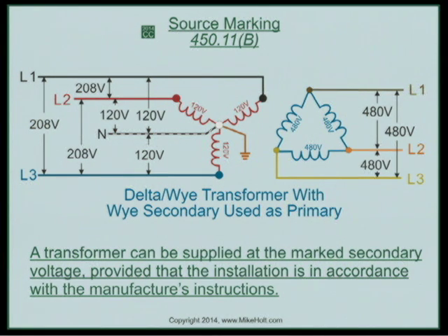Okay. Now, we're not getting into it, but we could easily have balanced out these loads and then go back to the windings. Let's put it this way. If this was a 45 kVA, the most you can have on any one phase would be how much? 15. So you couldn't put 25 kVA on line 1 and line 2, and then put 10 on line 2 and line 3, and line 1 to line 3, because that would, of course, translate itself to the winding.